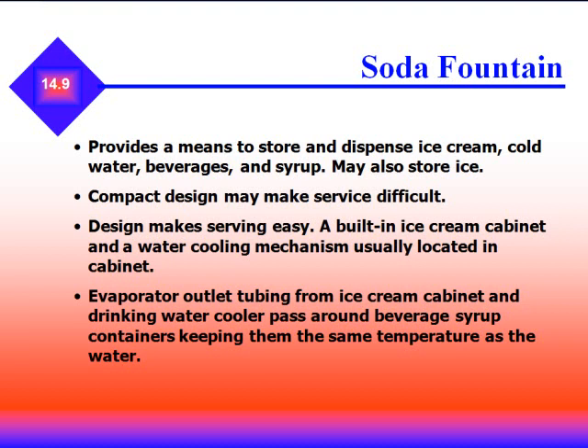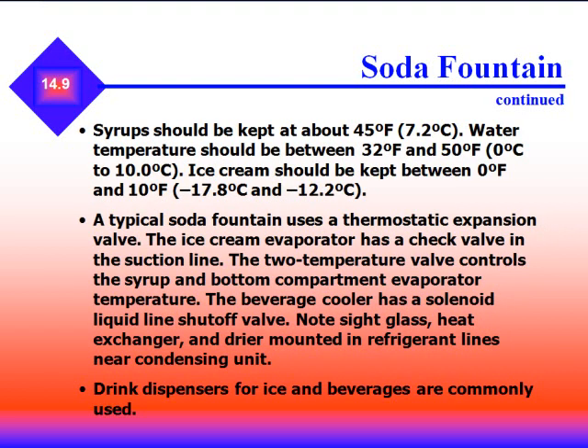Soda fountains store and dispense ice cream, cold water, beverages, and syrup, and may also store ice. A built-in ice cream cabinet and water cooling mechanism is usually located in the cabinet. Evaporator outlet tubes from ice cream cabinets and drinking water coolant pass around a beverage syrup container, keeping them at the same temperature as water. Syrup should be kept at about 45°F, water between 32 and 50°F, and ice cream between 0 and 10°F. A typical soda fountain uses a thermostatic expansion valve, with the ice cream evaporator having a check valve in the suction line, a two-temperature valve controlling the syrup compartment evaporator, and a solenoid liquid line shutoff valve on the beverage cooler.